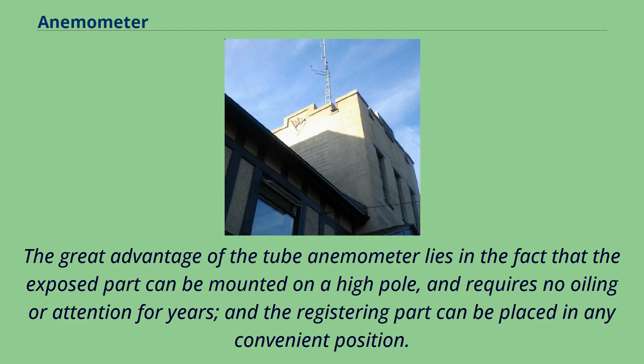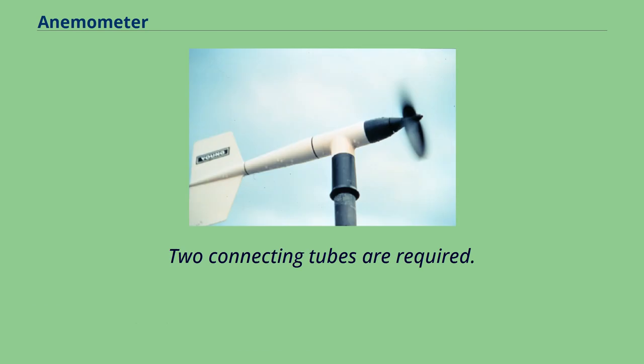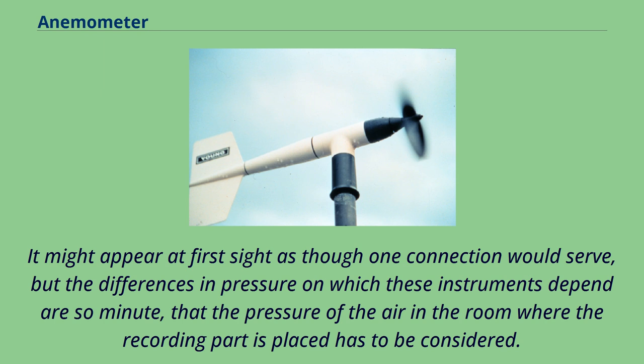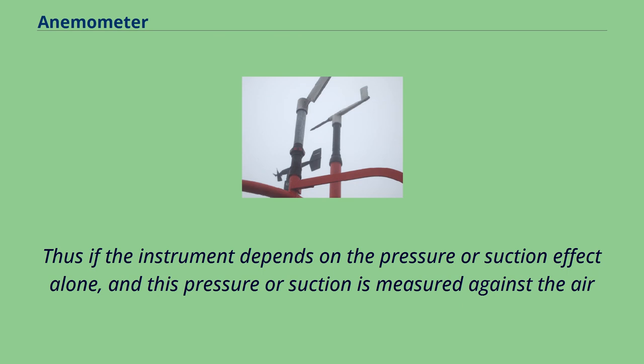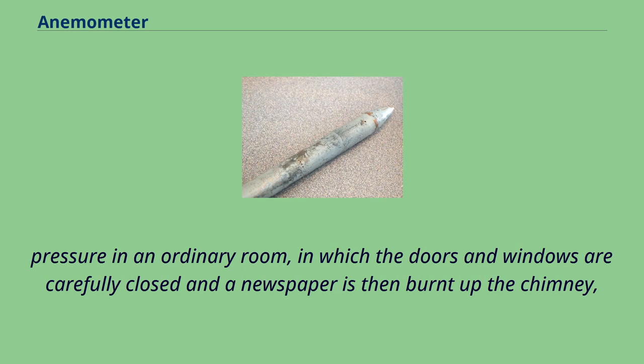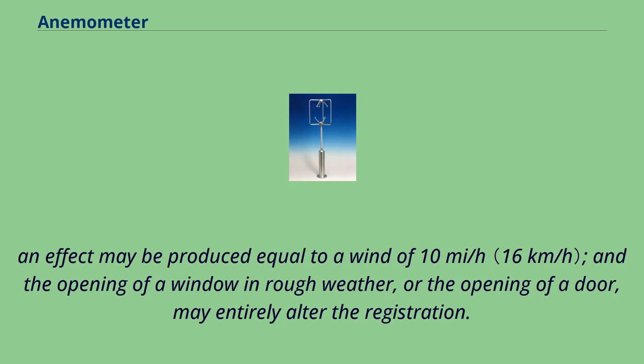The great advantage of the tube anemometer lies in the fact that the exposed part can be mounted on a high pole, and requires no oiling or attention for years, and the registering part can be placed in any convenient position. Two connecting tubes are required. It might appear at first sight as though one connection would serve, but the differences in pressure on which these instruments depend are so minute, that the pressure of the air in the room where the recording part is placed has to be considered. Thus if the instrument depends on the pressure or suction effect alone, and this pressure or suction is measured against the air pressure in an ordinary room, in which the doors and windows are carefully closed and a newspaper is then burned up the chimney, an effect may be produced equal to a wind of 10 miles per hour, and the opening of a window in rough weather, or the opening of a door, may entirely alter the registration.